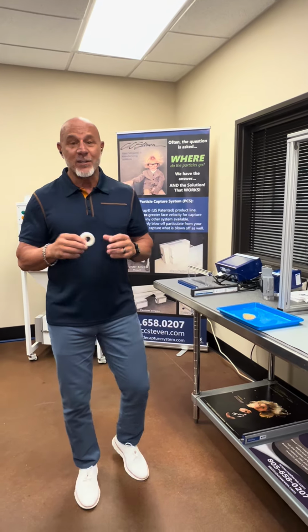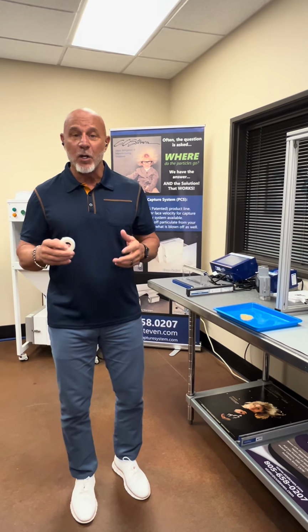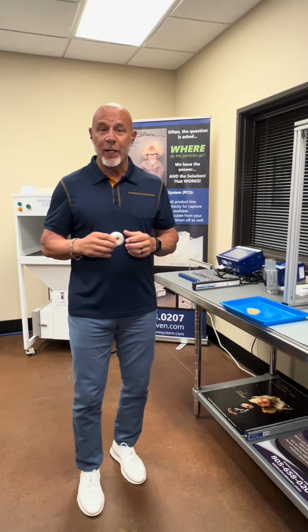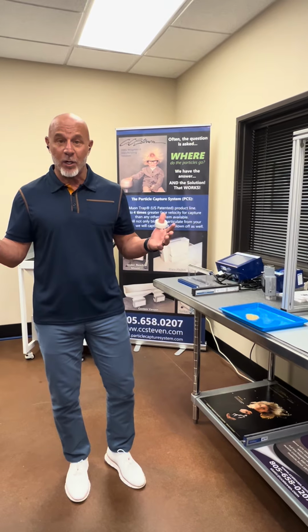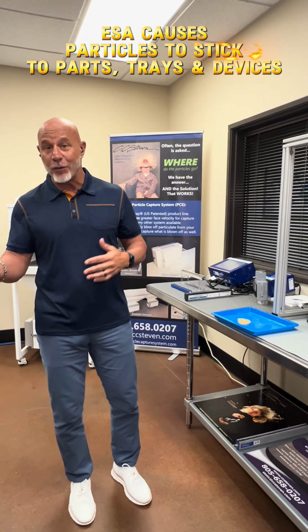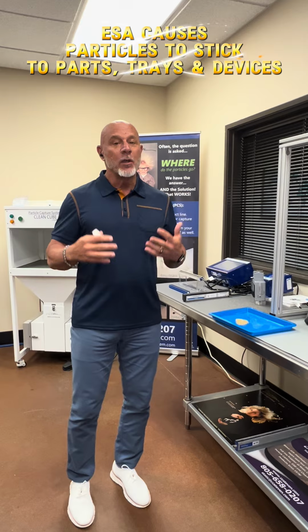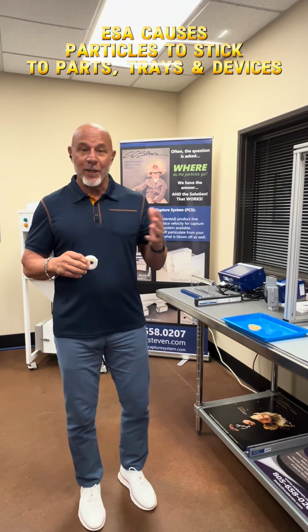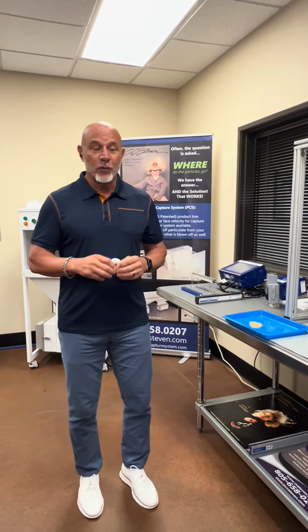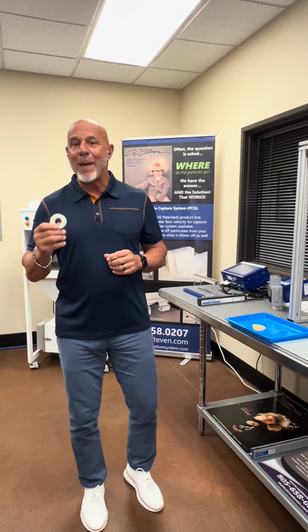First of all, let's talk about the manufacturing area in general. Everything is done in med device spaces and life science spaces in clean rooms. What's a clean room? A clean room is designed to air scrub particles out of that room and keep it clean. But those particles need to be airborne, and airborne particles can get scrubbed through that clean room concept. But ESA, electrostatic attraction, will cause those particles to stick to your product, to your chairs, to your shelving, to the floor, and thus not allow us to scrub those particles out of our system, thus making our clean room really not that effective. So today I'm going to talk about ESA, electrostatic attraction, how it affects your process, and how we battle and deal with that.